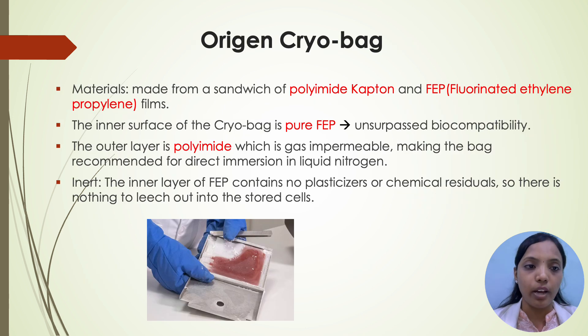Coming to Origen cryobags: the material is made from a sandwich of polyimide, Kapton and FEP — fluorinated ethylene propylene — films. The inner surface of the cryobag is pure FEP, which has unsurpassed biocompatibility. The outer layer is polyimide, which is gas impermeable, making the bag recommended for direct immersion in liquid nitrogen. It is inert — the inner layer of FEP contains no plasticizers or chemical residuals, so there is nothing to leach out into the stored cells.